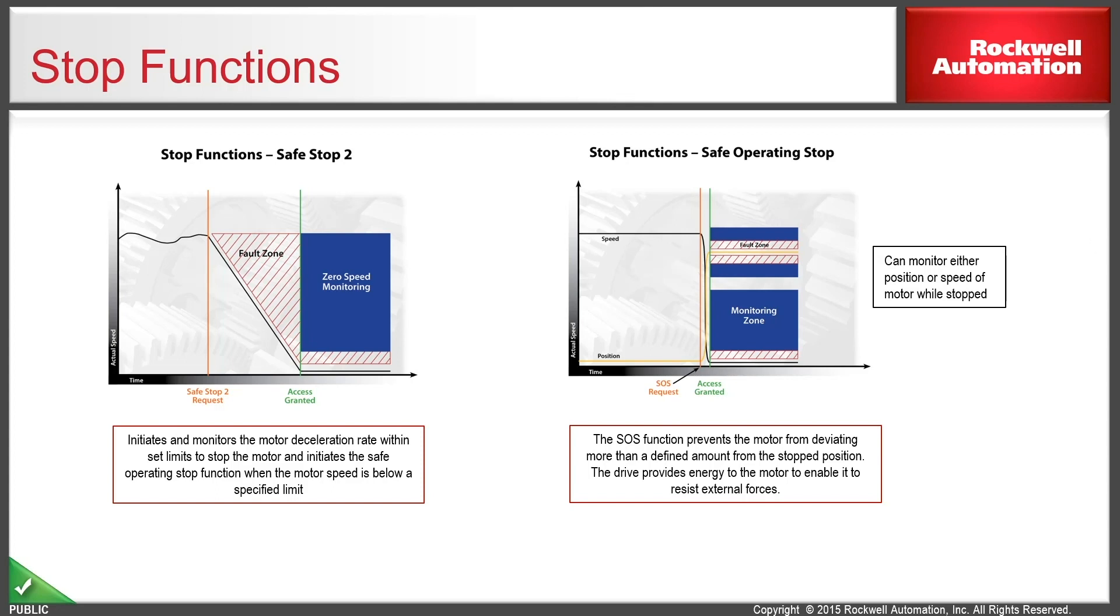A couple of other safety functions that revolve around stopping would be a safe stop two function. A safe stop two function would be where you bring the drive to a controlled stop and then you leave the drive enabled after you bring the axis to a stop. So a safe stop one is a ramp to a stop and turn the drive off. A safe stop two is a ramp to a stop and then you leave the drive enabled. The difference though is again not only that you're leaving the drive enabled but typically at the end of a safe stop two you would transition into something called the safe operating stop where you're doing zero speed monitoring or zero position change monitoring.